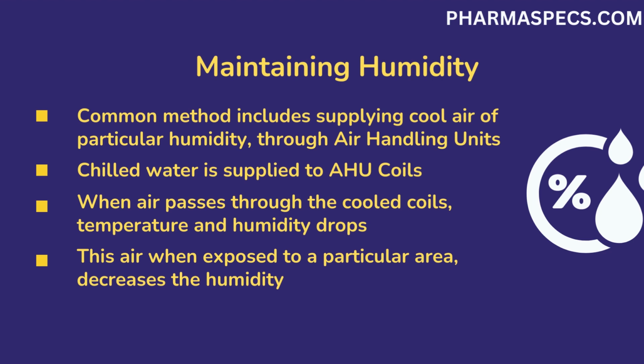Humidity levels are controlled by supplying cool air having particular humidity levels. These are achieved in the air handling unit. When air passes through cooled coils, temperature drops. Lower temperature also decreases the air's humidity and it becomes dehumidified. The dehumidified air, when exposed to an area, decreases the surrounding air's humidity level. The humidity levels are maintained by continuously supplying the dehumidified air to the area.